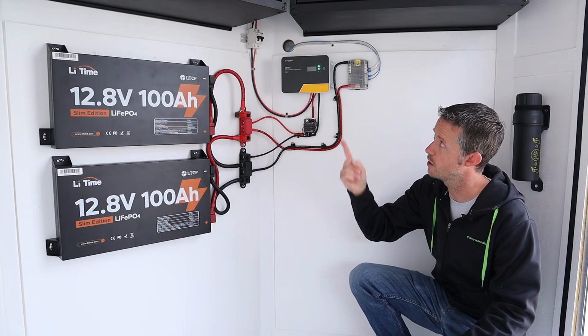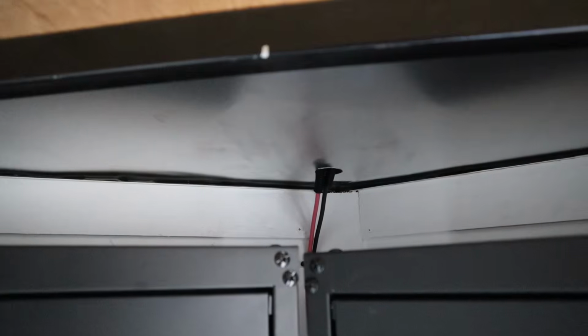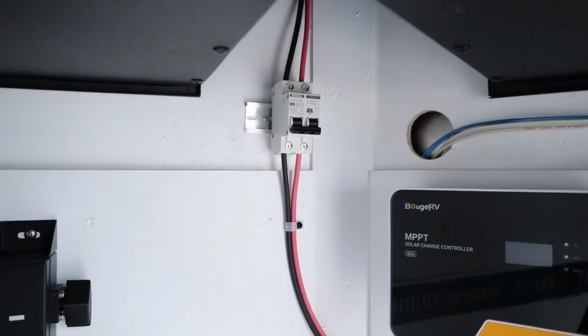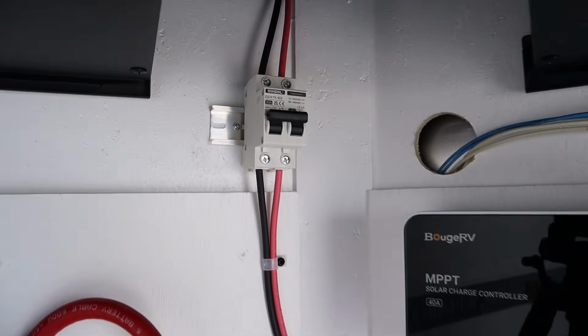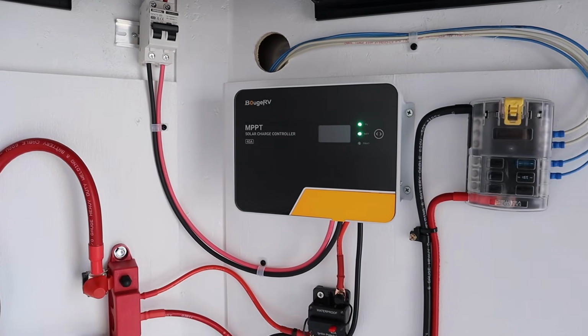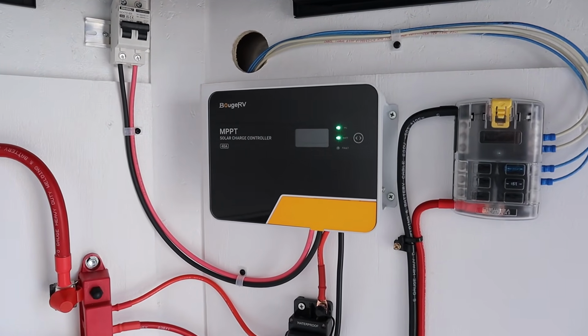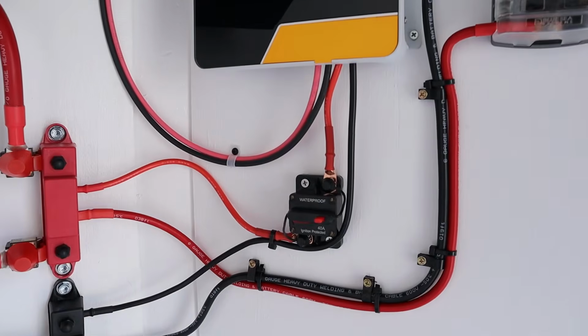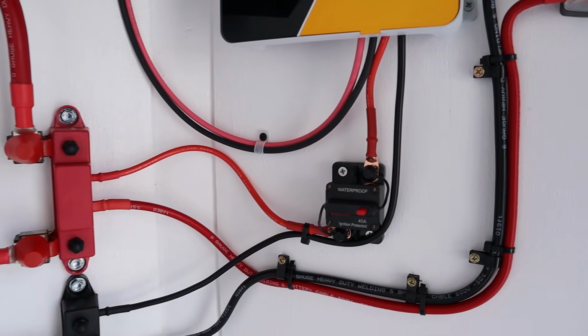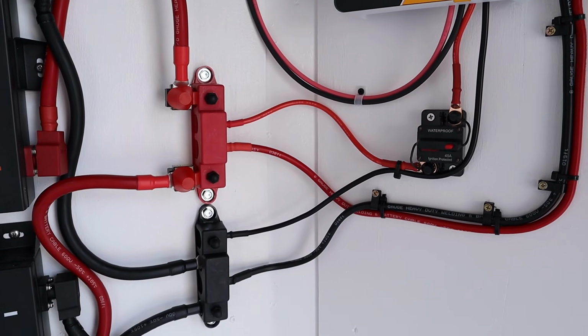I still have the 300 watts of solar panels on the roof. I have 10 gauge wire that comes through the roof down the wall through a 30 amp DC breaker or DC disconnect. Then it goes into the PV input of the 40 amp charge controller. Now, because it's a 40 amp charge controller, I am using 8 gauge wire coming out of that into a 40 amp DC breaker, which is connected to the bus bars.